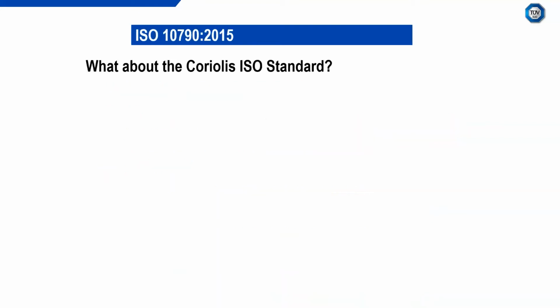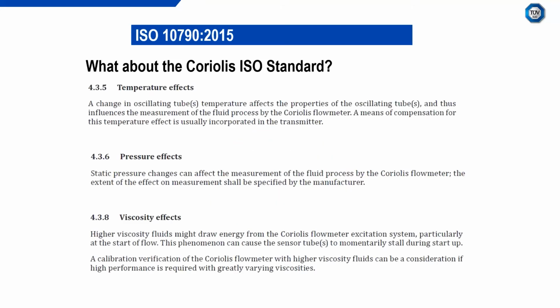What about the ISO standard? So that's the 10790. That was last revised in 2015. It's up for revision this year. It's still to be voted upon in ballot whether it's to be revised or not. Personally, I hope that it is, because I think there's a lot of data NEL have gathered and would like to share that with the standard to hopefully inform industry. But this is, again, some snippets from the ISO standard. Again, I'm not going to read it all out verbatim. I'm just going to put it up on the screen. You can scan through it if you wish. Ultimately, the standard tells you that there is temperature compensation in a Coriolis meter.